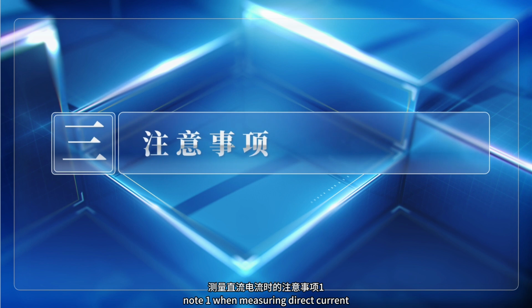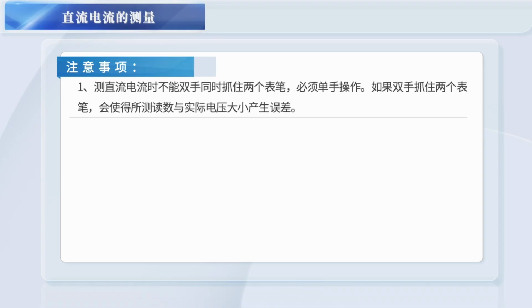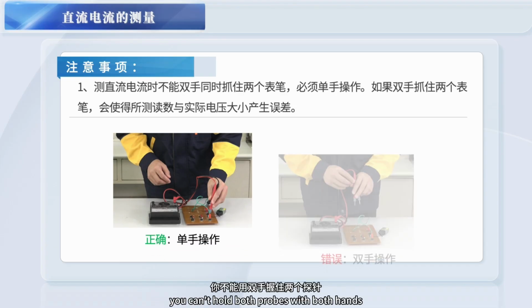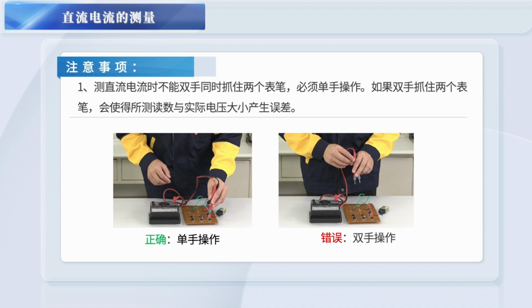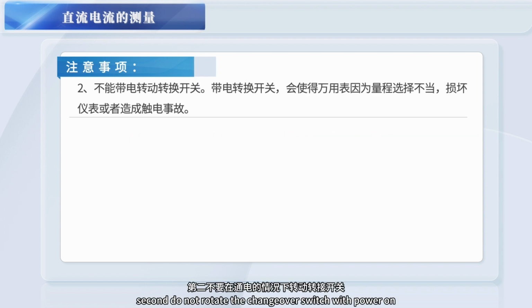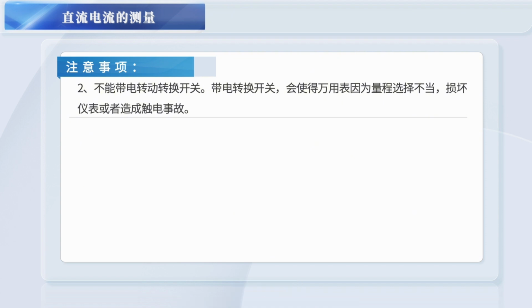Note 1. When measuring direct current, you can't hold both probes with both hands. You must operate with one hand. If you hold both probes with both hands, the measured reading will be different from the actual voltage, resulting in errors. Second, do not rotate the changeover switch with power on. Otherwise it will cause the multimeter to be damaged or cause electric shock.